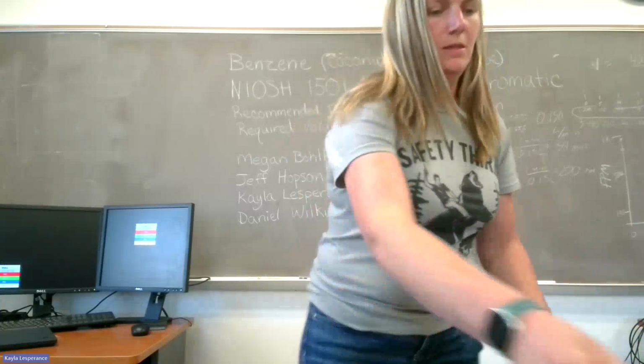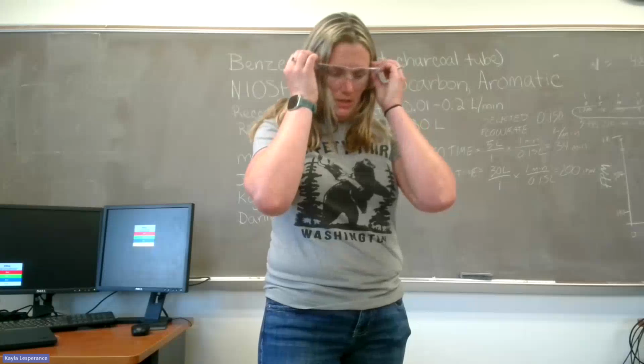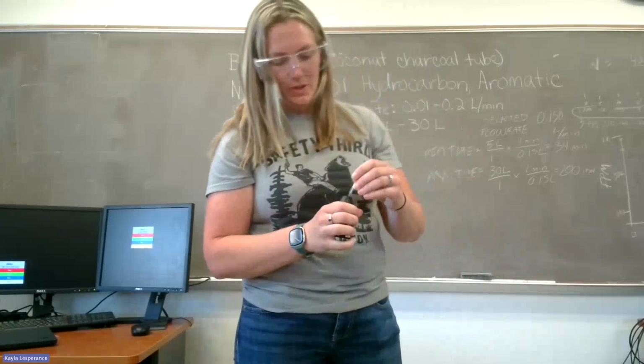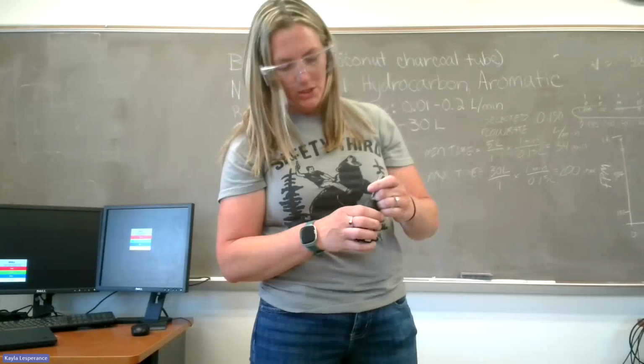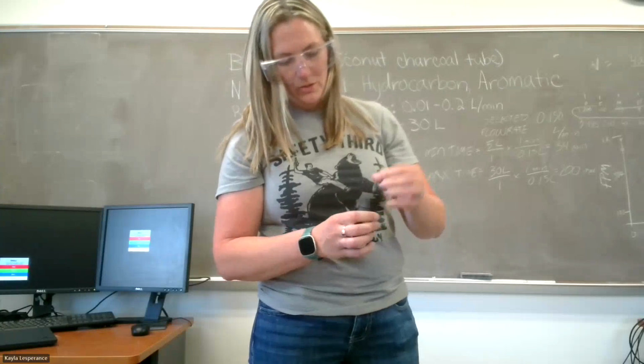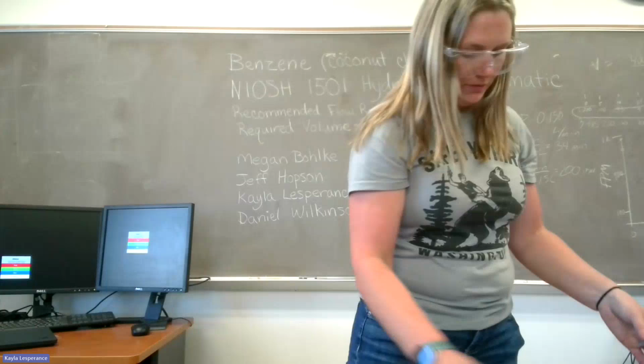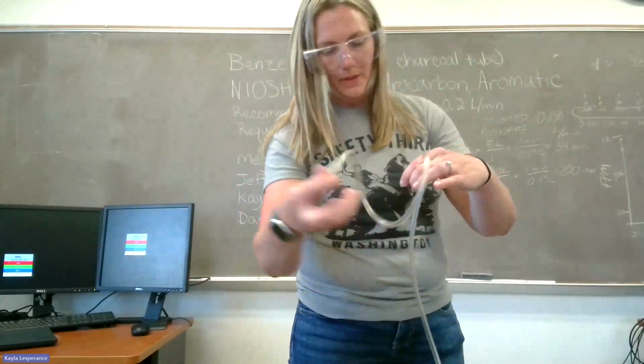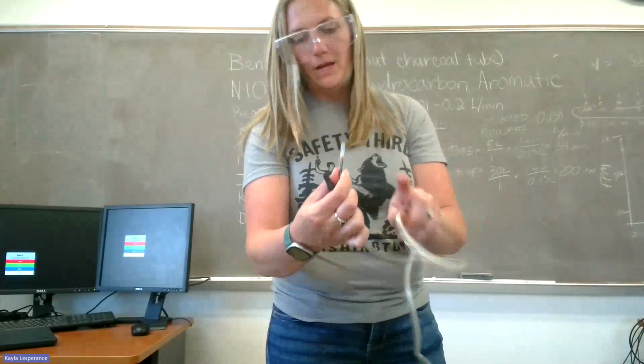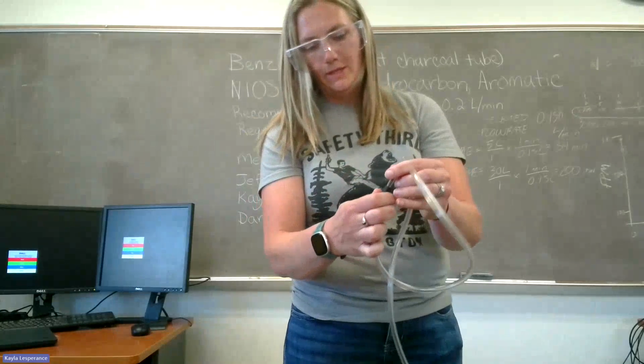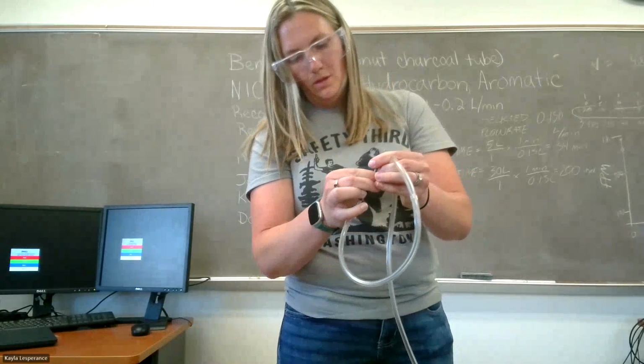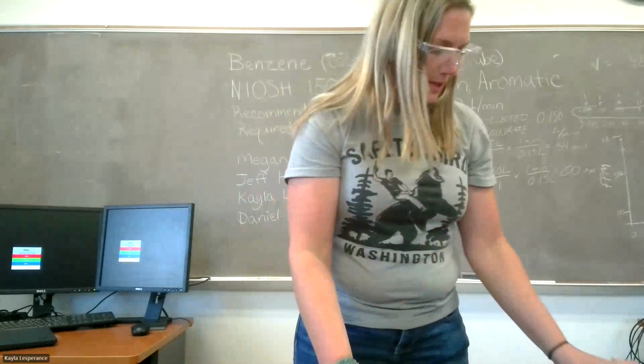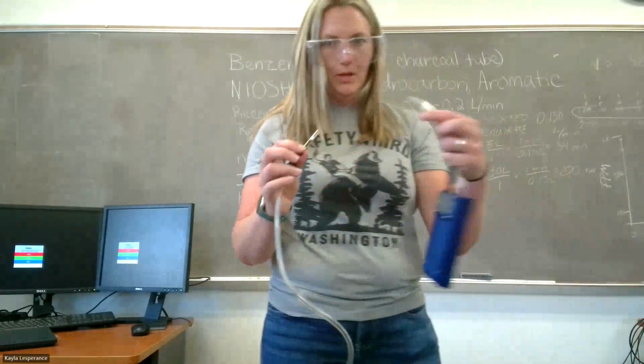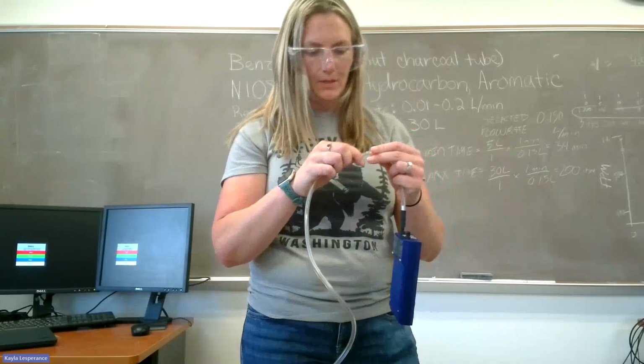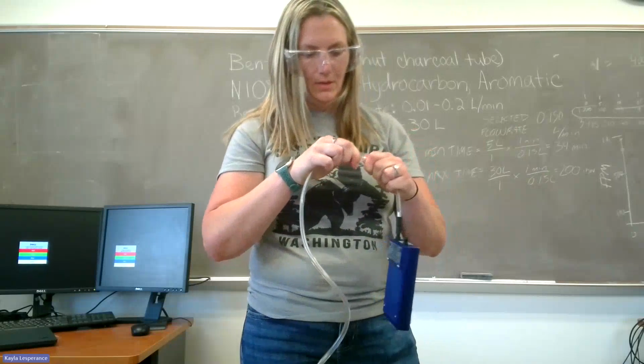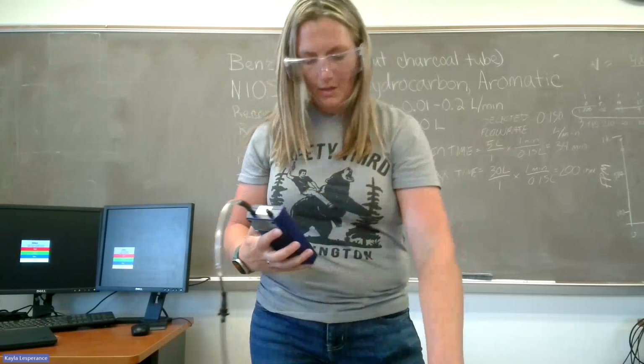So the first thing is safety first. And we will break open our calibration tube and score the edges and then break the end of the tube off. And then on the pump itself, we're going to verify that the arrow is the direction of airflow desired, so always to the pump. And insert that there. And then hook it up to our Checkmate. Get a good seal. Make sure that's not slipping.